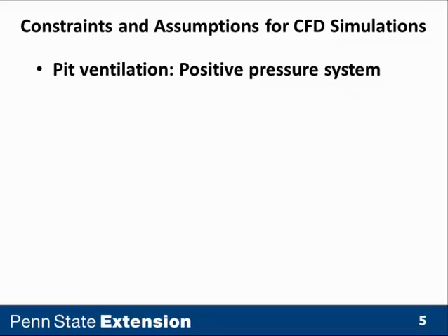We chose positive pressure because many, especially slotted covered manure storage pits, are very sensitive to short circuiting, and a positive pressure system is a little more forgiving than is a negative pressure system in short circuited ventilation situations.